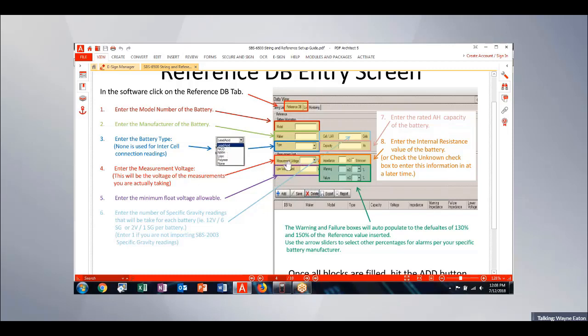And then I'd enter the measurement voltage for that particular battery. So if I've got an individual 2-volt flooded cell, I'd set that at 2 volts. If I had a nickel cadmium battery, I'd set that at 1.2 volts. Whatever the nominal voltage of the block measurement that you're going to be taking is. Low voltage limit: manufacturers usually publish a minimum recommended float voltage for that particular battery model, that voltage which the battery shouldn't drop below when it is being charged or in float service. And that's the value that I enter for low voltage limit. I want to know if any of my batteries aren't charging correctly.